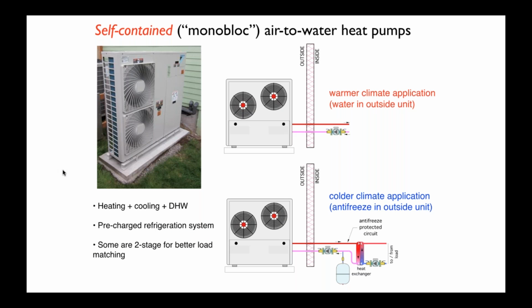Okay, there's a couple common configurations for air-to-water heat pumps. I refer to one of them as a self-contained. The common term, and I believe this term came out of Europe, it's called a monobloc, and it actually is spelled that way without the K. Monobloc, when you hear that term, what that means, the heat pump is self-contained. All the components of the refrigeration system, the controls, everything is in that box, and it's factory charged with refrigerant. To install it, you need to physically place it on a base. You need to connect 2 pipes and the electrical to it, but you don't need to get out tanks of refrigerant and start charging it.